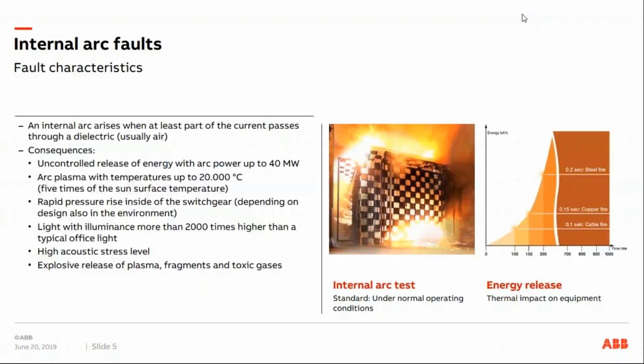Also, what you could see is the arc plasma with temperatures up to 20,000 Celsius, which is 5 times the sun surface temperature. A rapid pressure rise inside of the switchgear if you're having a metal enclosed compartment, depending on the design, also in the environment, and light with illuminance more than 2000 times higher than the typical office light. High acoustic stress levels, as we could all hear, explosive release of plasma, fragments, and toxic gases, which are quite dangerous for everyone working in a switchgear environment.